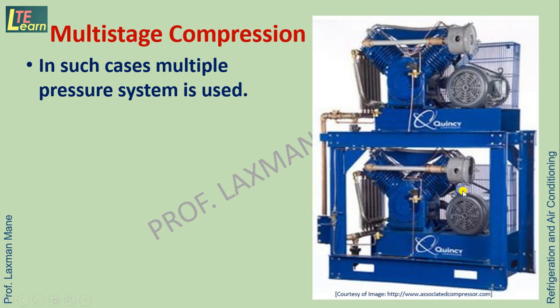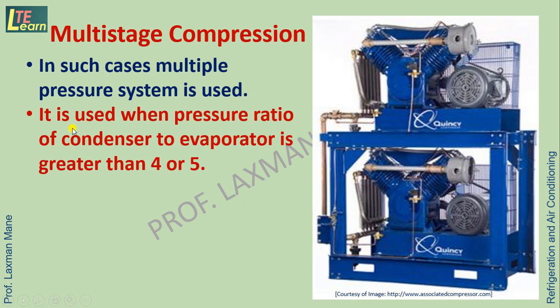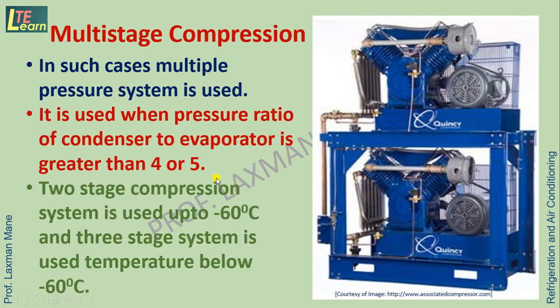In such cases, a multi-stage compressor — a multiple pressure system — is used. It is used when the pressure ratio of condenser to evaporator is greater than 4 or 5. A two-stage compression system is used up to minus 60 degrees Celsius evaporator temperature, and a three-stage system is used for temperatures below minus 60 degrees Celsius.